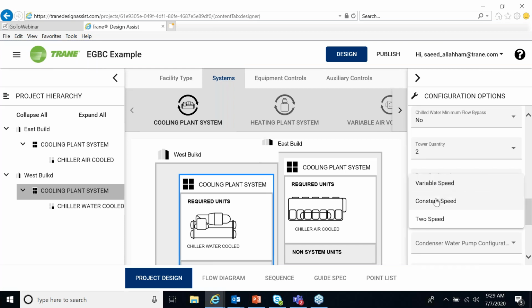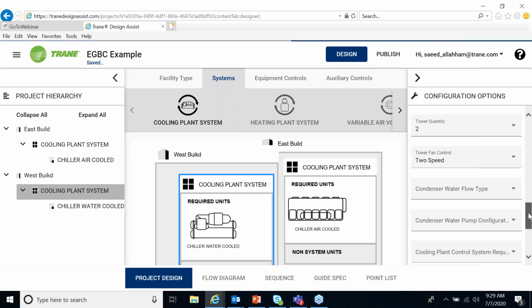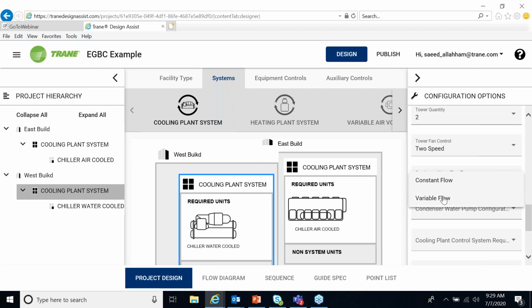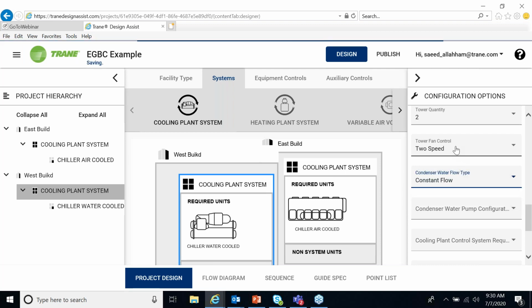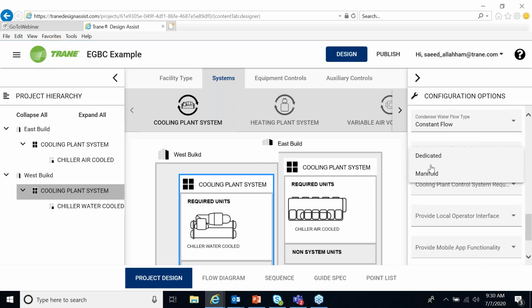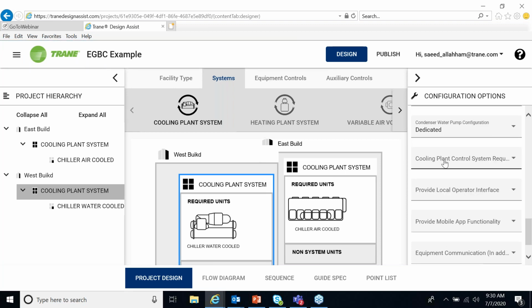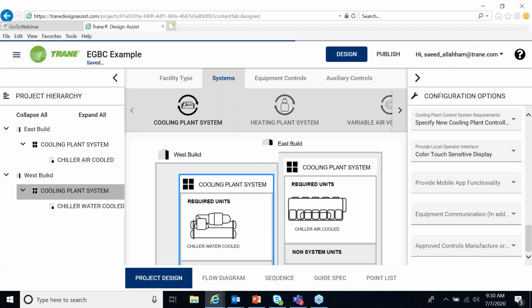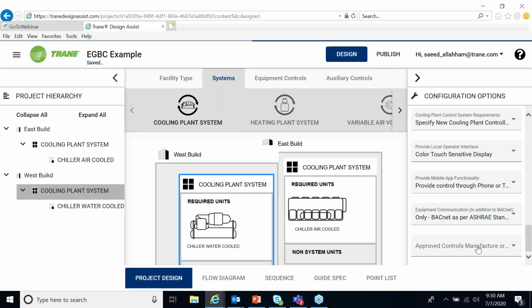Tower fan control, we have the variable speed or constant speed or 2 speed. Let's say we have 2 speed cooling tower. Condenser type, the condenser can be constant flow or variable flow. So based on that one, it will select the type of control. For example, we can have constant flow for the tower. We can make it variable speed. The condenser pump, it can be dedicated or manifold. Let's see the dedicated first, and then we look to the manifold. New cooling plant. So we are doing here the configuration of the cooling plant.